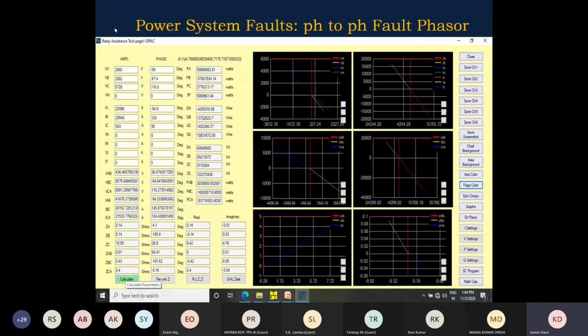So this is how you look at it. The phasors are exactly opposite, currents IA and IB. You look at it here. And impedances, you look at it, ZA is 0.14, ZB 0.14, ZC is 10.55, which is very high, and ZAB is very low, 0.01, ZBC is 0.43, and ZCA is 0.4.